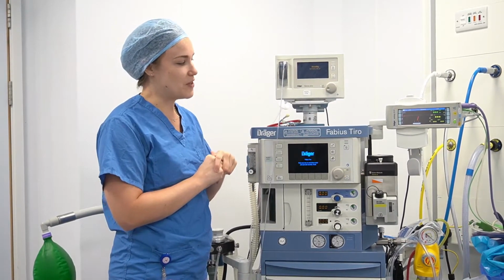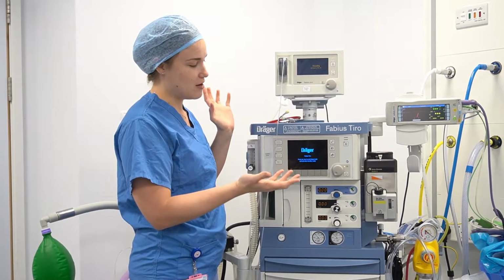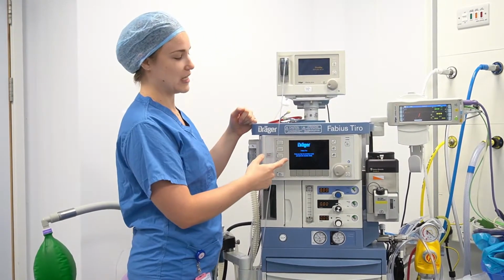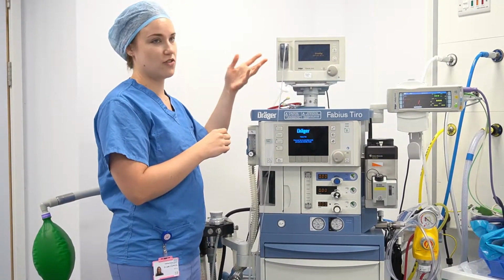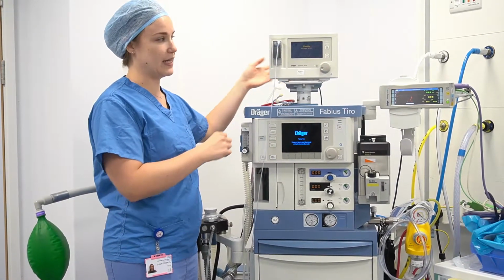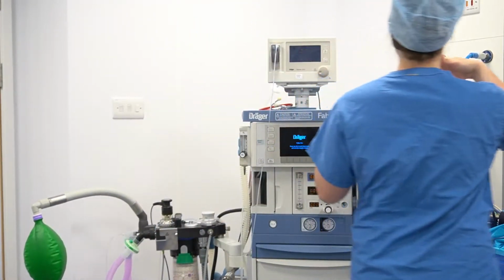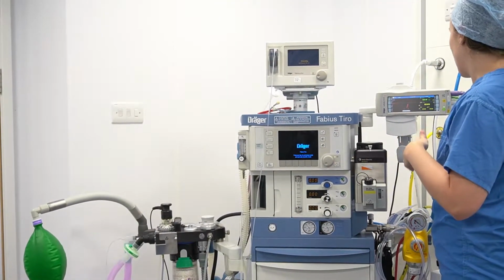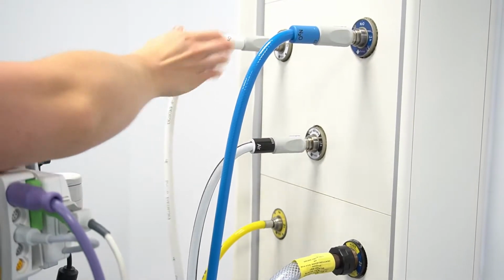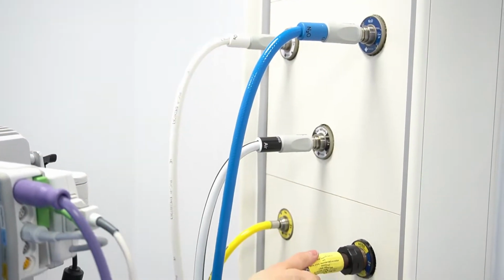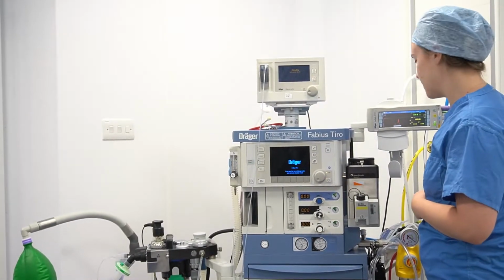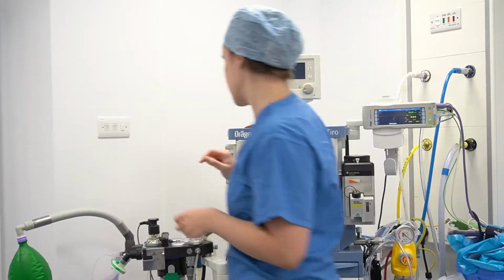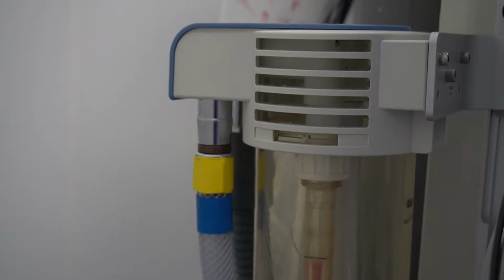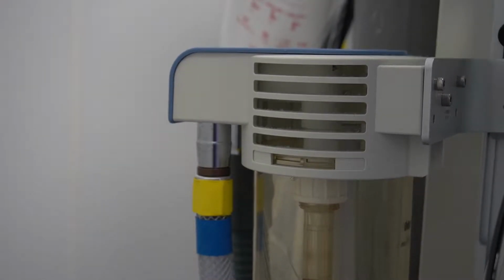a list. So we'll first just make sure when you come in, the machines will most likely be in sleep mode and will look like this. And then obviously, if not, check that it's actually connected to the power supply, which will be at the back of the machine and then connected to the wall. While you just check that this is working, you can just do a tug test for all your gases. Make sure that your suction is connected correctly, and that also your scavenging system. And then just to check that your scavenging system is also connected to the machine itself at the back over here. And then you can see that the pipelines are connected to the machine itself, which is on the right side.